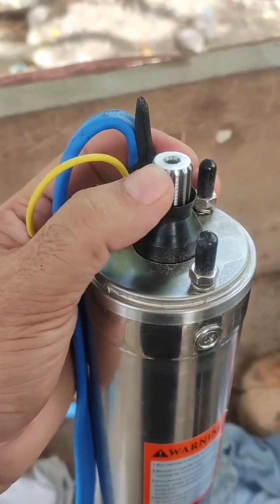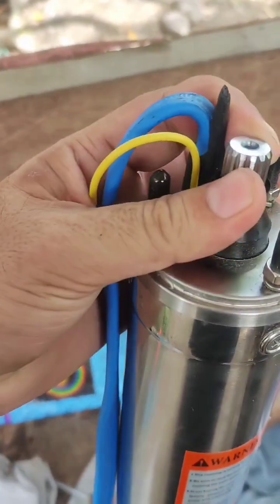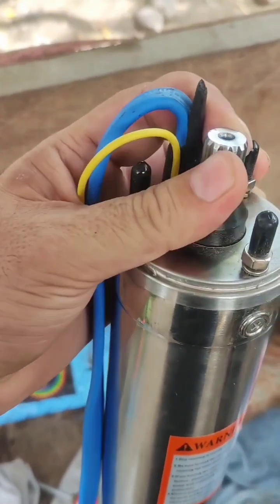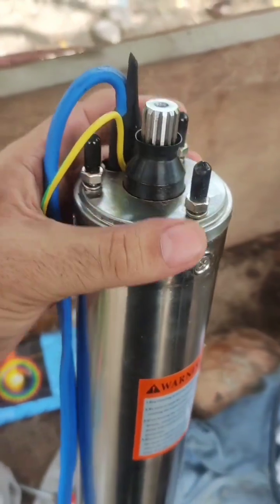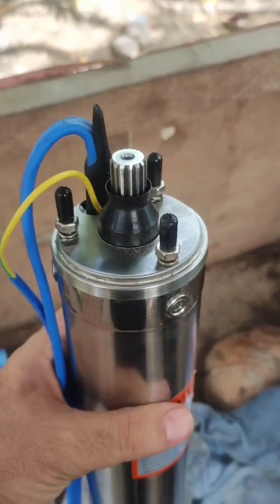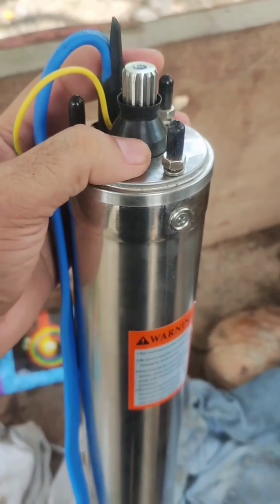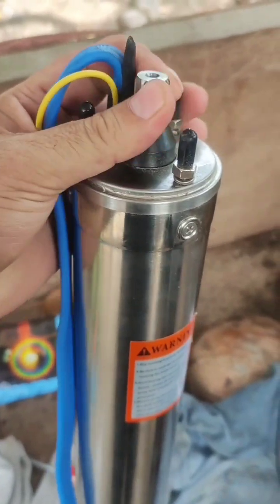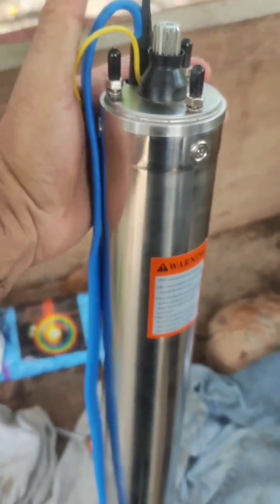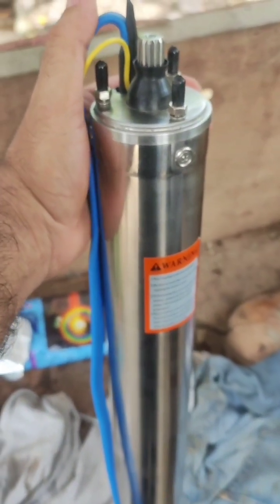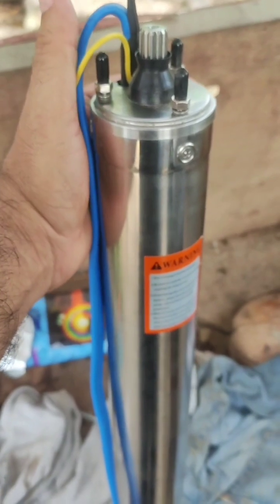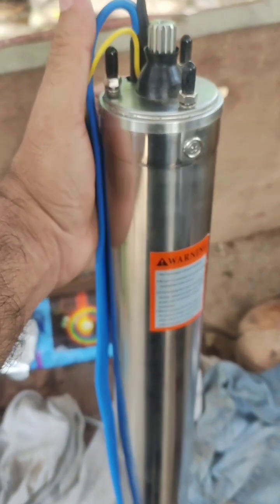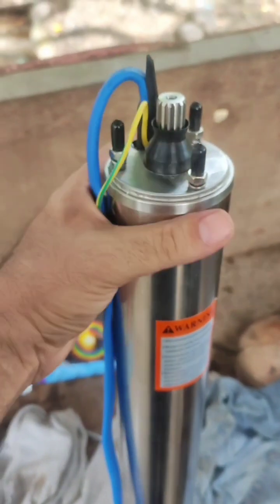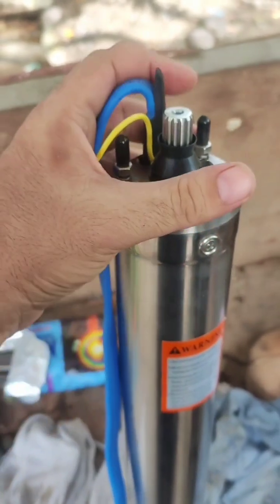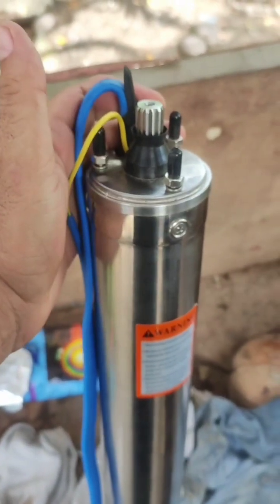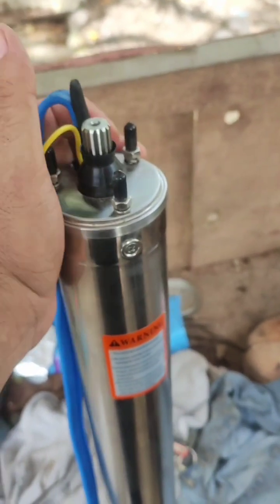Here you can see the shaft, very perfect balance. So now it's time to install the pump body. Motor test is complete, ready. The shaft is very smooth, perfect. It is prohibited to run dry for long, it cannot run, but only for test purposes we run it, and it's perfect now. So it's time to install the upper pump body and we will test it into the well.